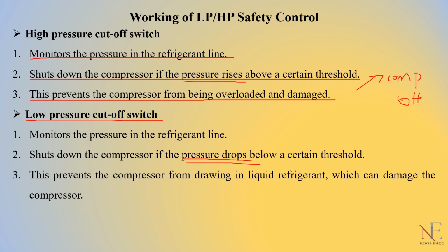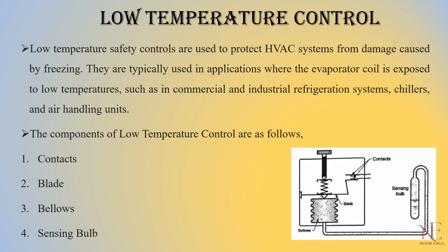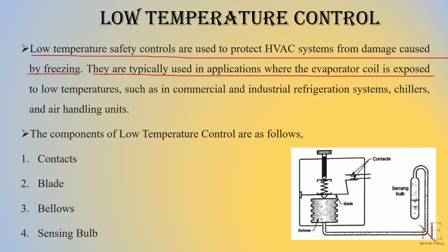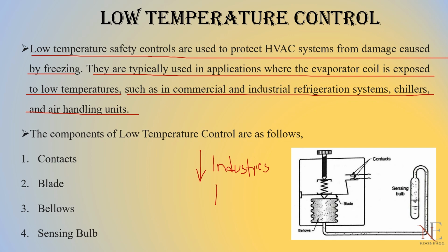Now let's move on to the second one. The next one is low temperature control. So what is a low temperature safety control? Low temperature safety controls are used to protect HVAC systems from damage caused by freezing. They are typically used in applications where the evaporator coil is exposed to low temperatures, such as commercial and industrial refrigeration systems, chillers, and air handling units. These are used where the temperature level drops to extremes, in industries where a very low temperature is needed, but there is a threshold point or set point.